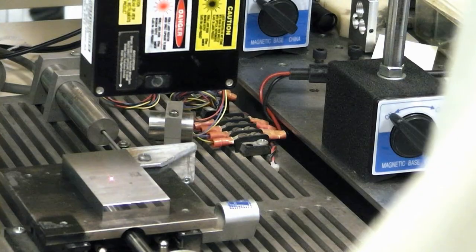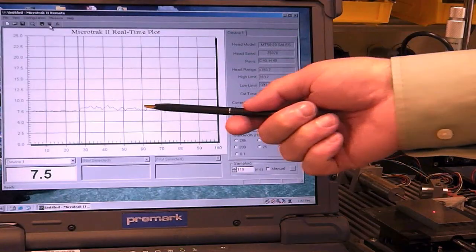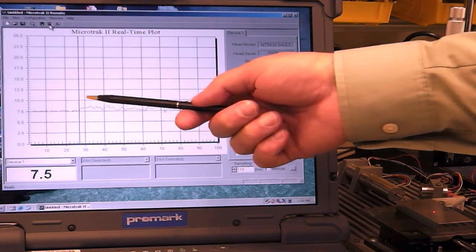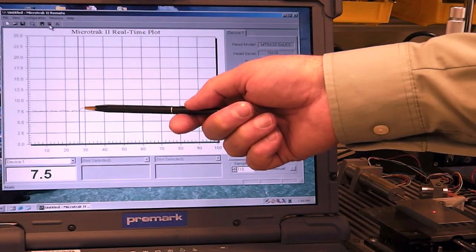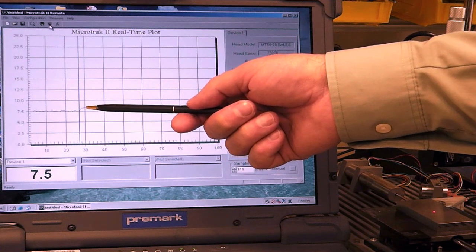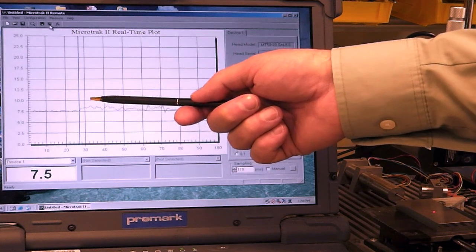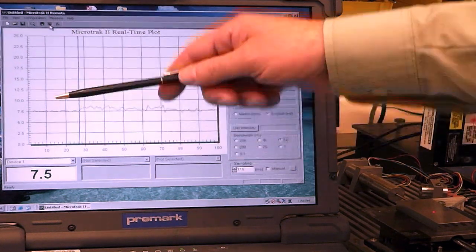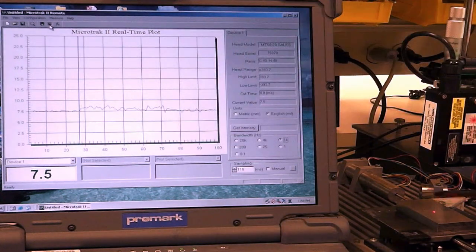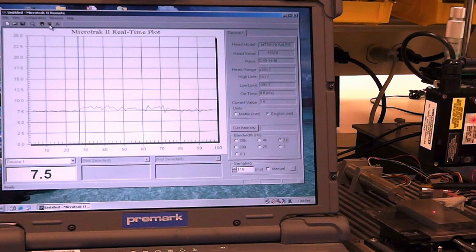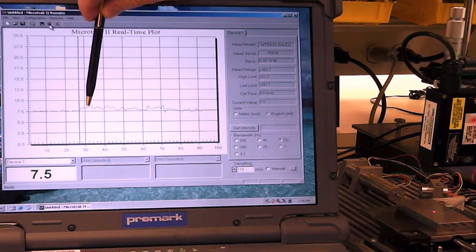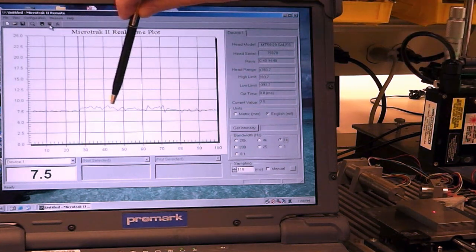That's about an inch. Here we're looking at the Microtrak II remote program. We have a sensitivity of about 2.5 mils per division, and I've translated the gauge block on the X-Stage. We can see that we're relatively flat.